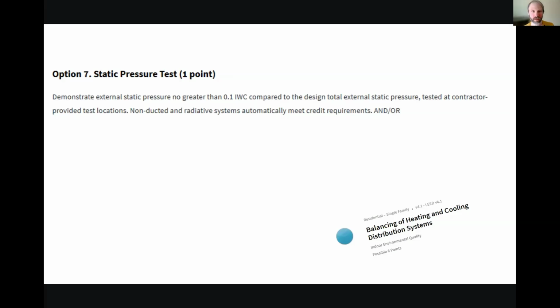So what you're trying to do with static pressures, you're trying to make sure that you're within 0.1 IWC, and we'll go into that, of the Energy Star for Homes design HVAC checklist of what we're trying to achieve. And again, that's supply and balancing, airflow testing. That's going to help get you to this.